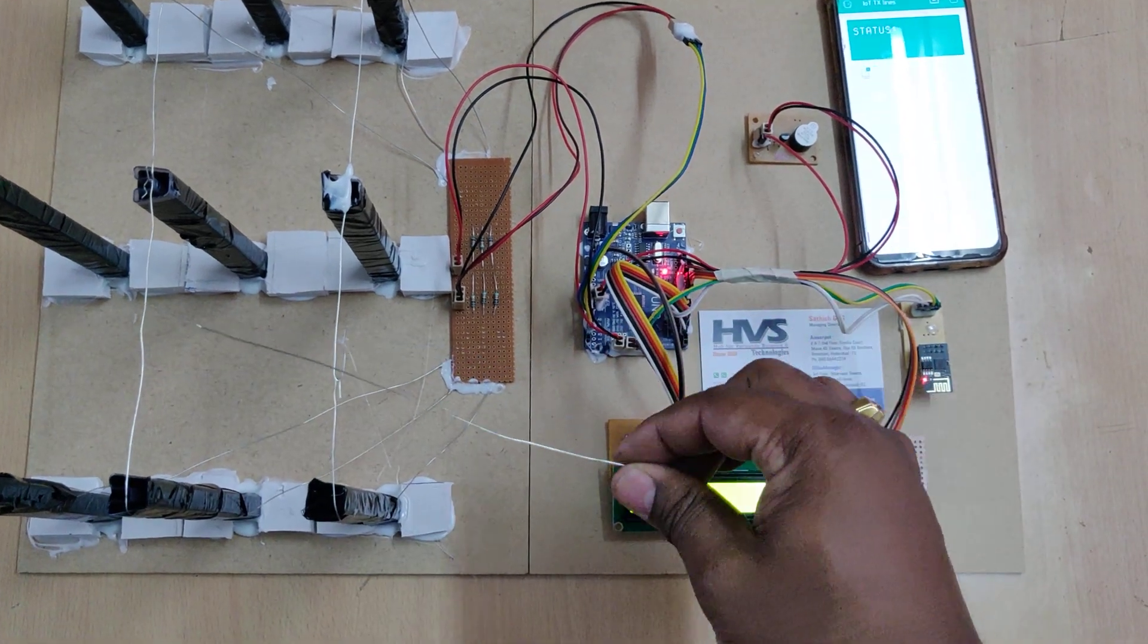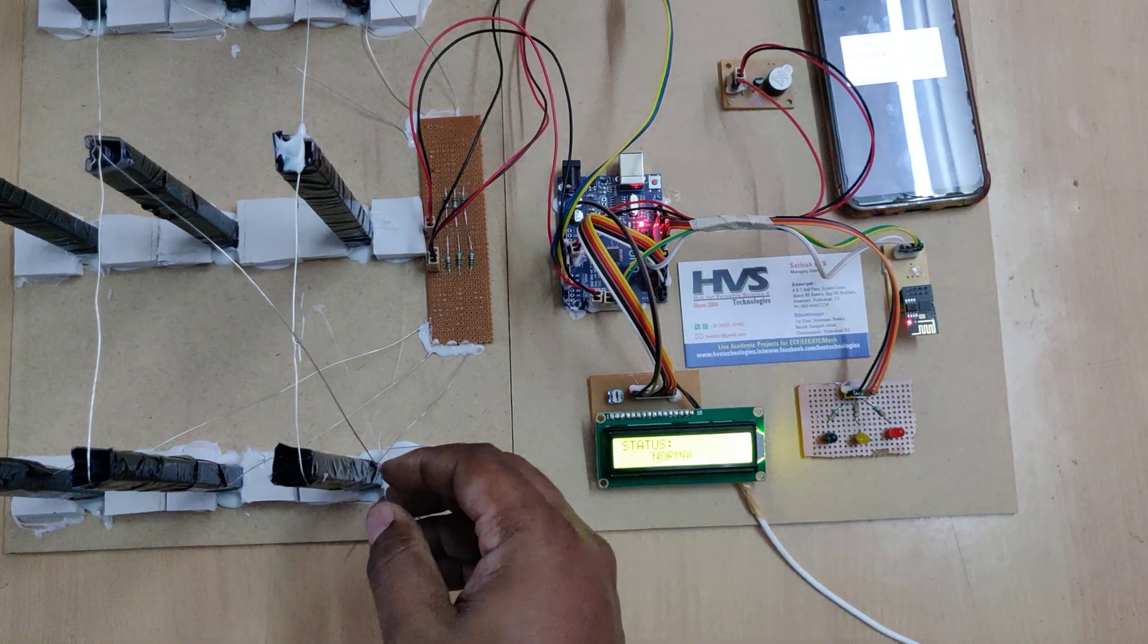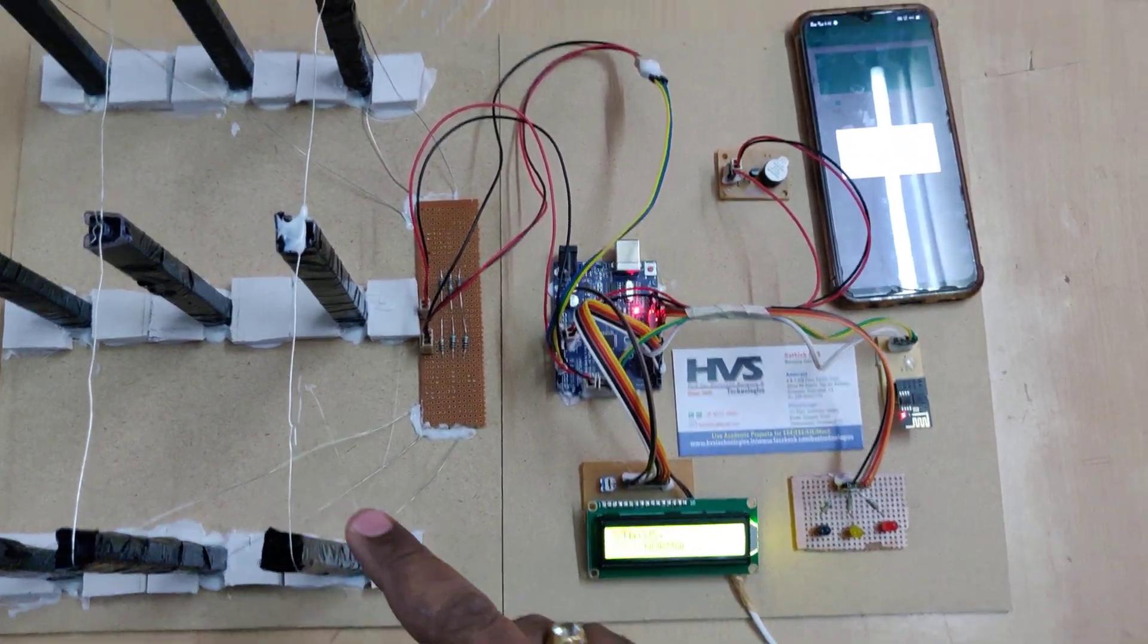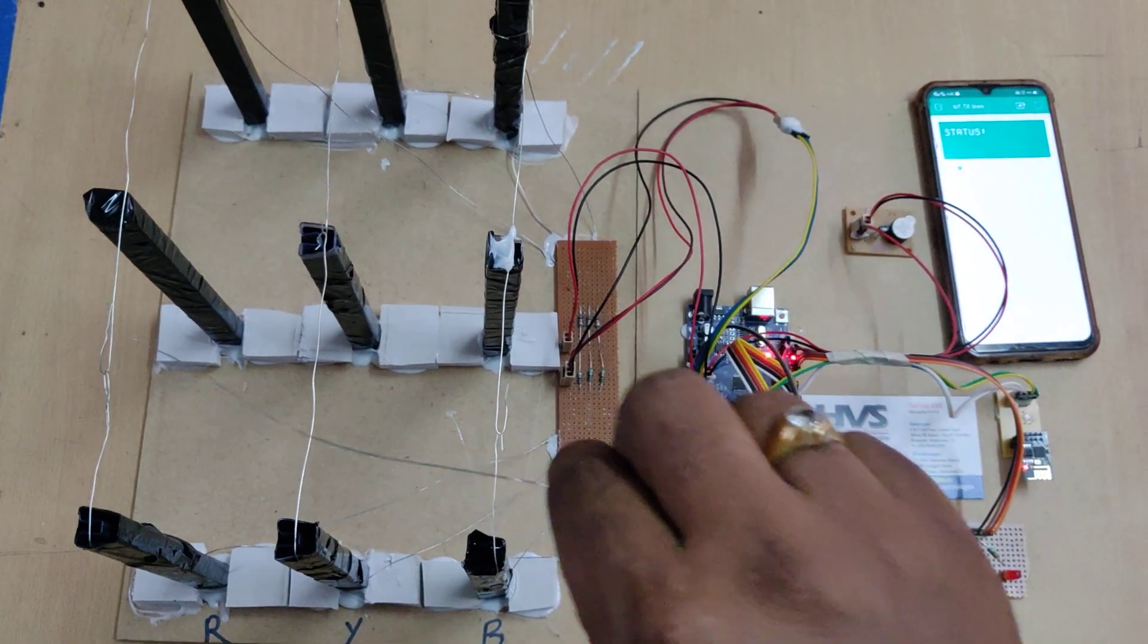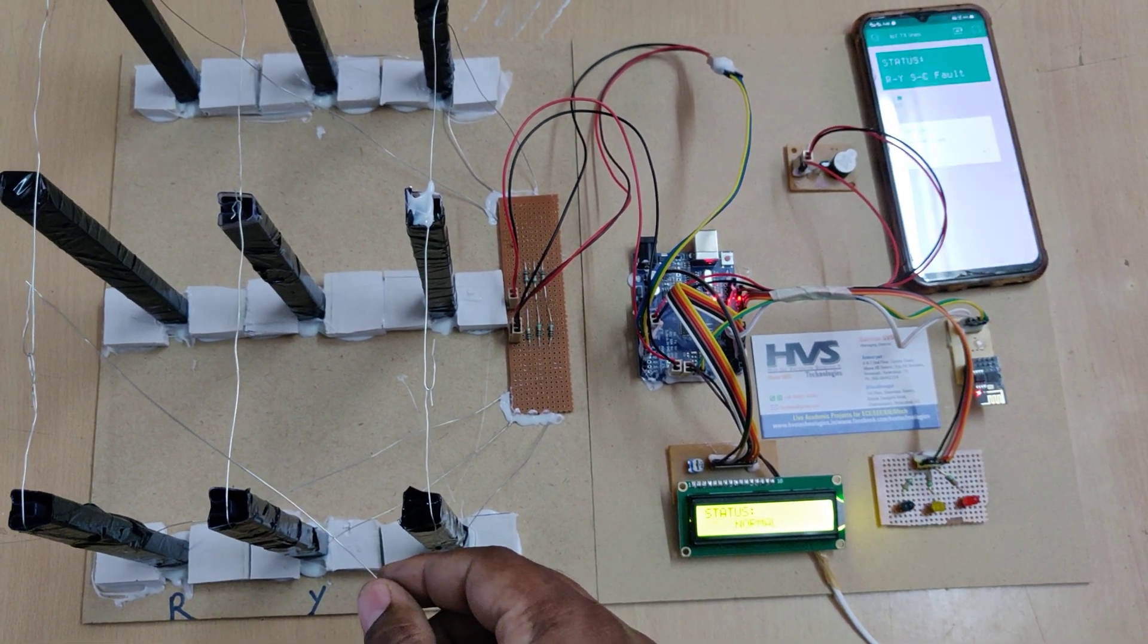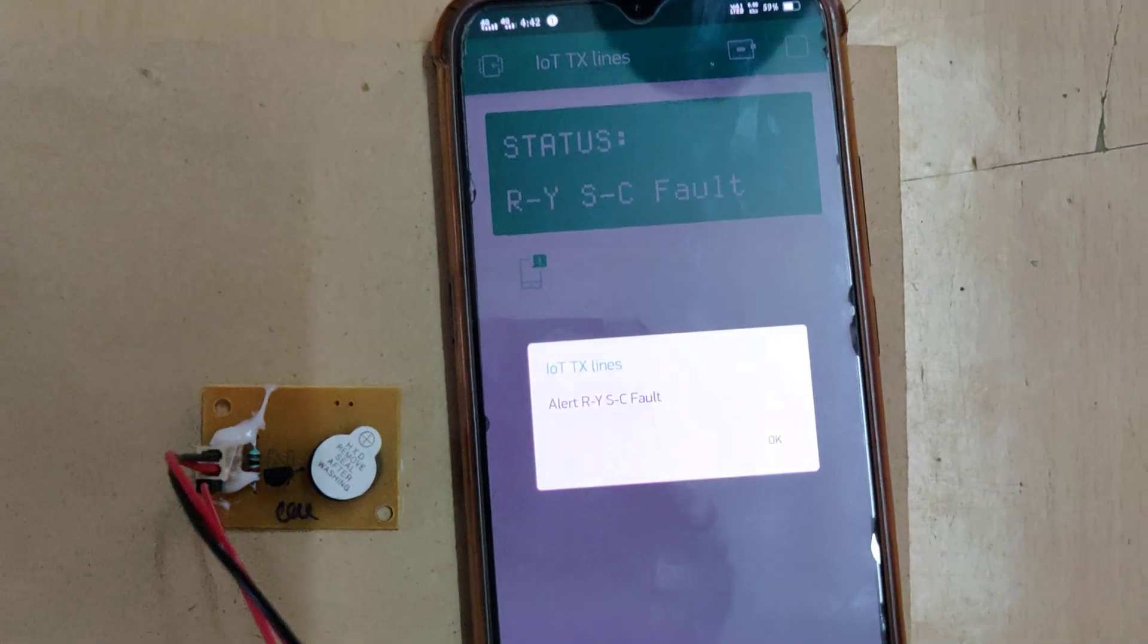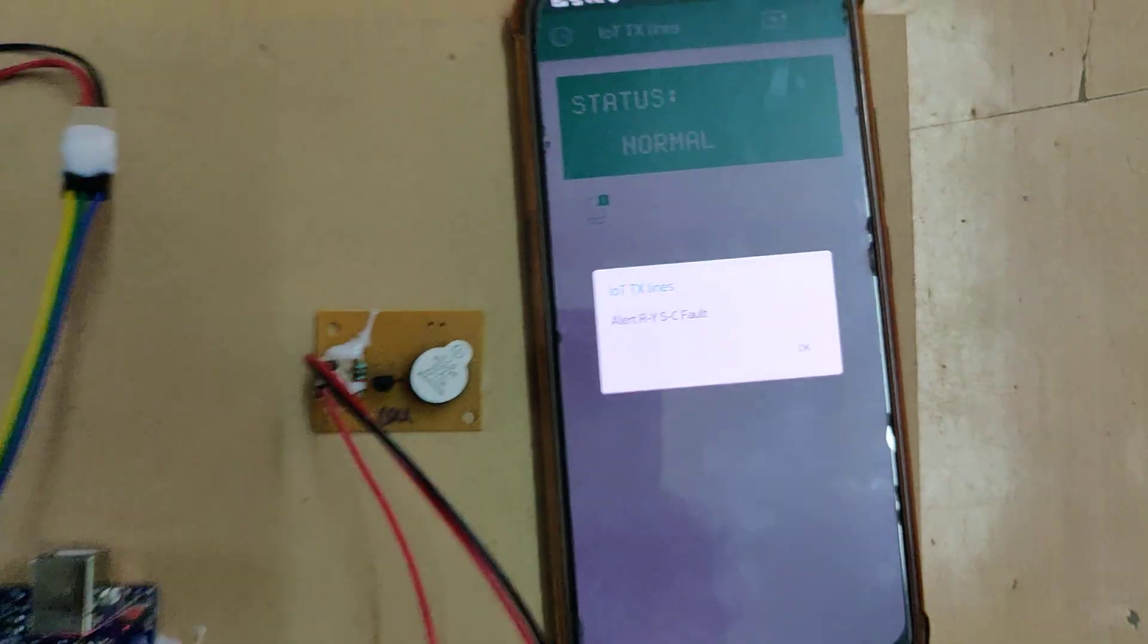So now I am making R, Y short circuit. This is R, Y, B. So I am making short circuit fault, shorting them. Then R and Y lights turn on. You will get the same alert message in your phone: R, Y, SC fault, nothing but short circuit fault.